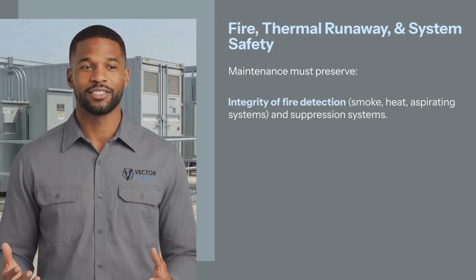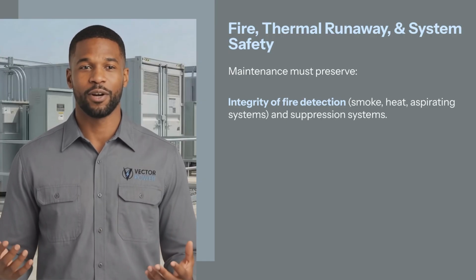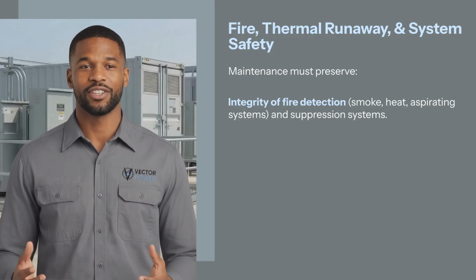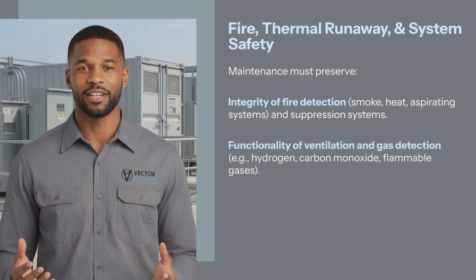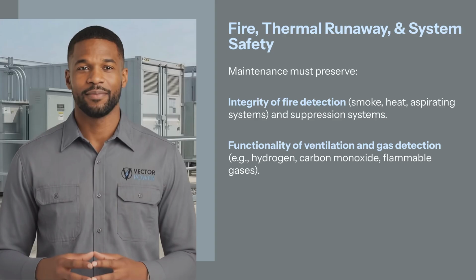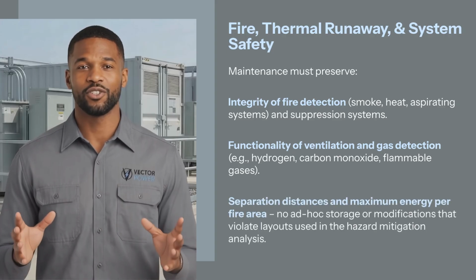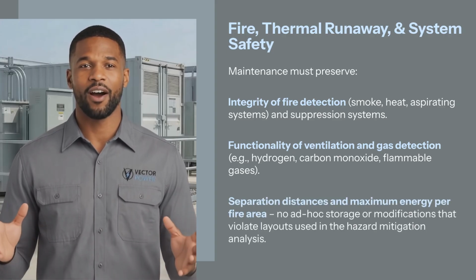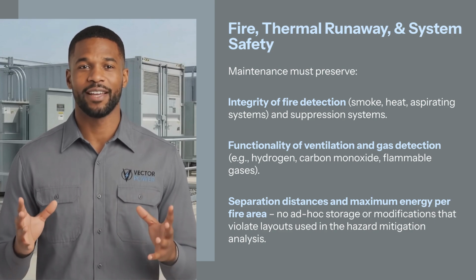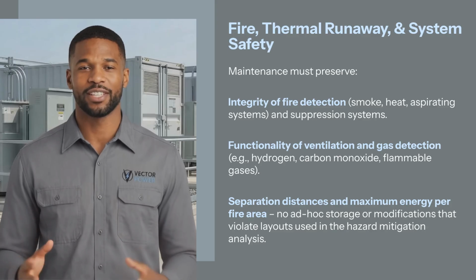Integrity of fire detection: smoke, heat, aspirating systems, and suppression systems. Functionality of ventilation and gas detection, for example, hydrogen, carbon monoxide, flammable gases. Separation distances and maximum energy per fire area. No ad hoc storage or modifications that violate layouts used in the hazard mitigation analysis.